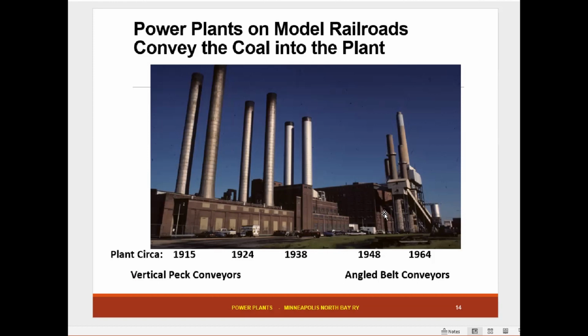And then this part was built after World War II. It's much bigger. This is at 900 pounds, 900 degrees. And now we have the efficiency. Down here, the efficiency is about 15%. Here is about 25% efficient. Here it's about 28%. And then the last unit they put in was pretty much the maximum for the regular units, 2,400 PSI at 1,000 degrees, and that's about 35% efficient. So it's about 5 times as efficient as the steam locomotive.